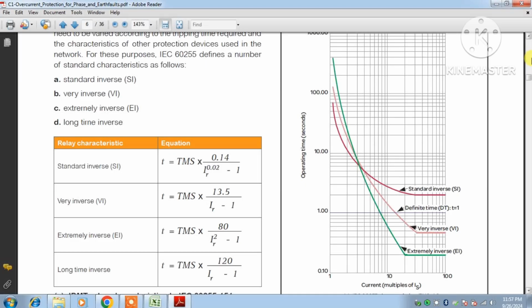Hello friends, today we'll discuss one more topic, that is the IDMT overcurrent relay. IDMT means inverse definite minimum time relay, and IDMT is actually a characteristic. It follows different types of curves. We'll discuss an application with which we can find the operating time of the relay when there is a fault, whether it follows a very inverse, extremely inverse, standard inverse or definite time curve. At which time the relay will operate, that calculation we can easily find out using a basis.